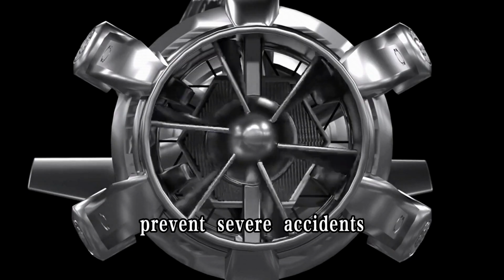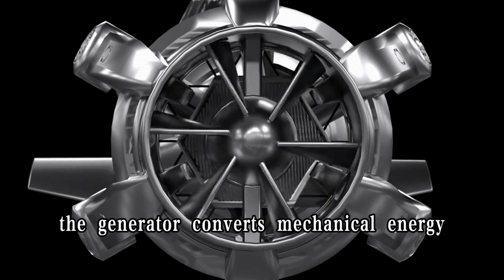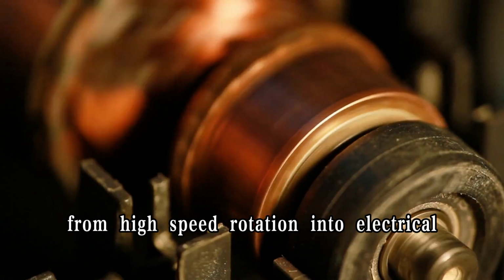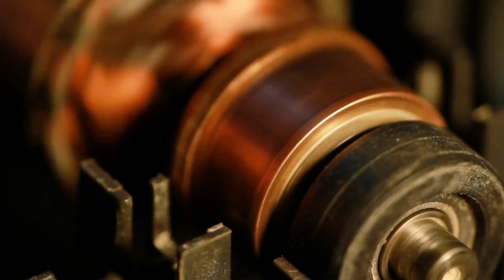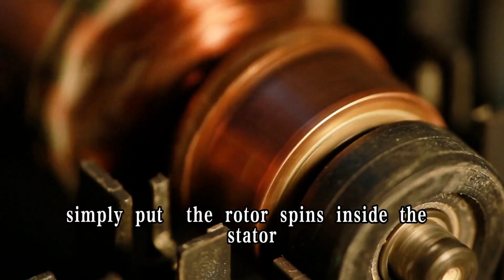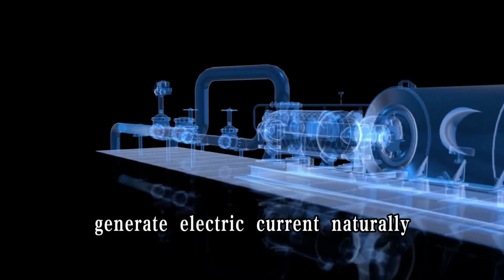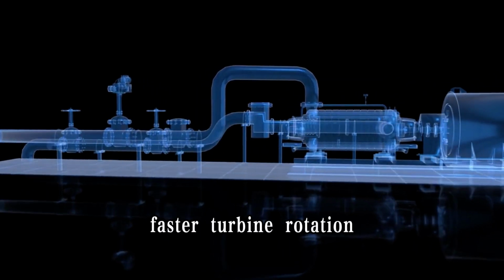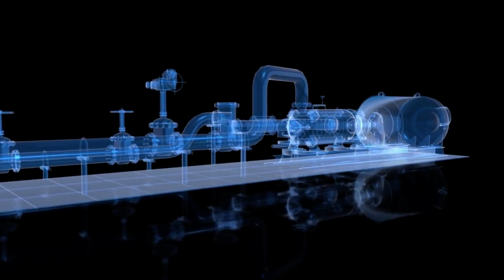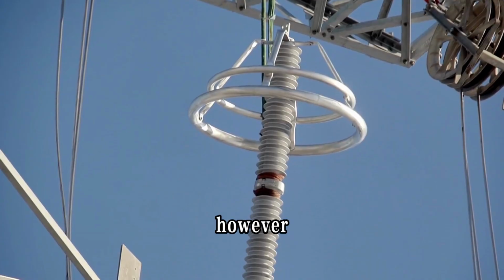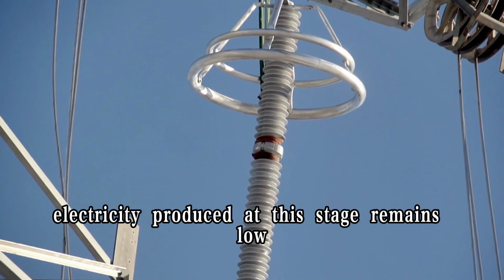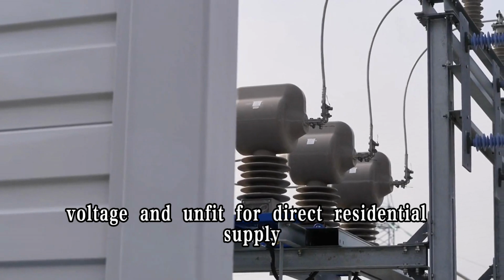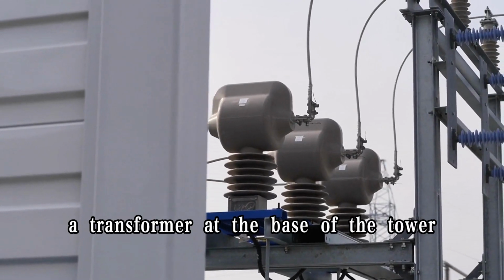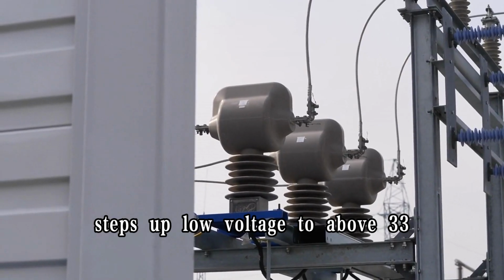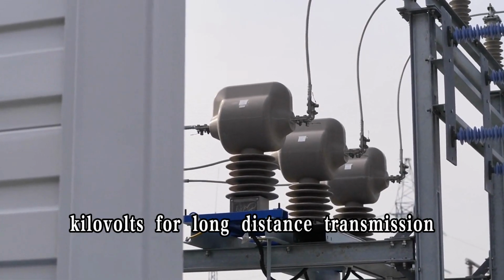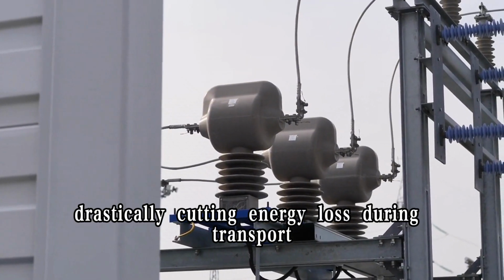The generator converts mechanical energy from high-speed rotation into electrical energy through electromagnetic induction. Simply put, the rotor spins inside the stator, cutting magnetic field lines to generate electric current naturally. Faster turbine rotation accelerates magnetic line cutting, yielding greater power output. However, electricity produced at this stage remains low voltage and unfit for direct residential supply. A transformer at the base of the tower steps up low voltage to above 33 kilovolts for long-distance transmission, drastically cutting energy loss during transport.